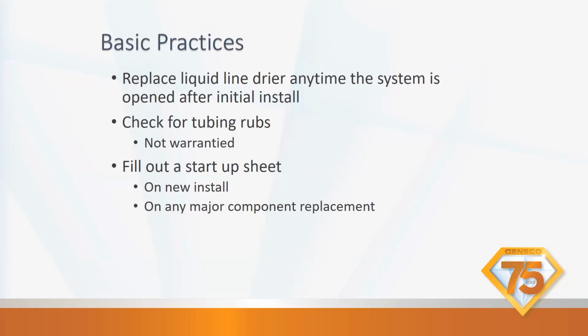Replace the liquid line filter dryer anytime the system is opened after the initial install, and make sure that you're installing it on install. It comes with the Trane American Standard units. You need to add it to an Ameristar and RunTru unit. So make sure you're putting one on every single unit.